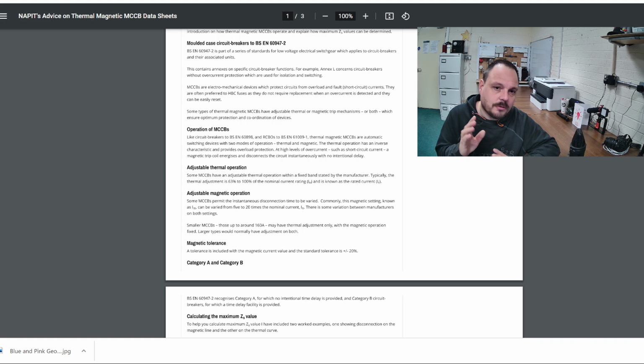So I referenced a video a while ago now. A 3-phase meter had exploded, and we'd had the operation of an upfront MCCB in a panel board, which was at the main intake cupboard for a row of industrial units, and then also at the affected unit itself. It had another sub MCCB in series with that one. They both operated, and then in the actual unit itself there was an MCCB used as the main switch, and that had operated as well. It was to do with transient voltage taking out a phase, which obviously upset everything, and all bets were off as to what would trip when and how, and the meter decided to spew its guts out and probably took the MCCBs with it. So that's just a demonstration that selectivity isn't always possible when you have a really serious short circuit fault. And I'll reference the link to that video somewhere at the top of here, so you can go off and check it out if you want.